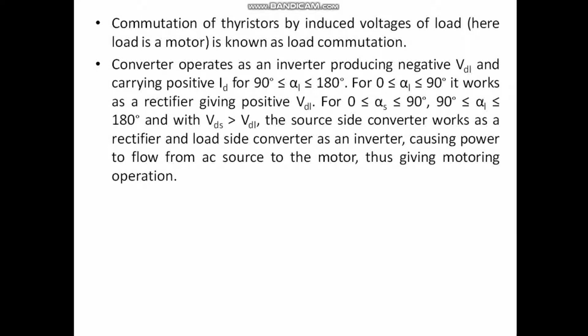Induced voltages we compare in the line commutated inverter. So we are comparing source side voltage and load side voltage. The source side converter works as a rectifier for the angles 0 to 90 degrees, and the load side converter acts as an inverter, causing power to flow from the AC source to the motor, thus giving motoring operation.